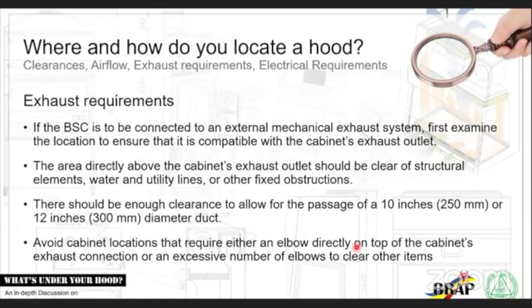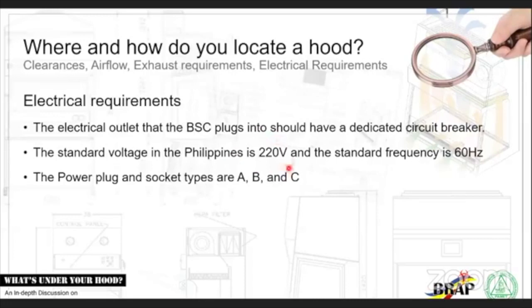Now, this is what I'm telling about. Avoid cabinet locations that require an elbow directly on top of the cabinet's exhaust, because this prevents your engineers from getting on top of your biosafety cabinet and doing the air measurements. Okay. Now, electrical requirements. In the Philippines, we have 220 volts and the standard frequency of 60 hertz. So, you have to look into this.